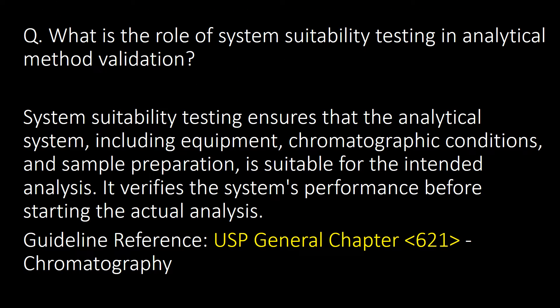What is the role of system suitability testing in analytical method validation? System suitability testing ensures that the analytical system — including equipment, chromatographic conditions, and sample preparation — is suitable for the intended analysis. It verifies the system's performance before starting the actual analysis. Guideline reference: USP Chapter 621.